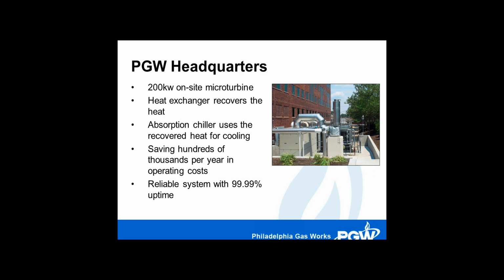Our CHP system has three major components. The picture on the right shows the microturbine and the heat recovery system. The three components are the microturbine, a heat exchanger - the small box to the right of the microturbine with the big stack coming out of it - and finally the absorber, which is inside the plant and cannot be seen. We have a 200 kilowatt microturbine here, a very quiet unit.